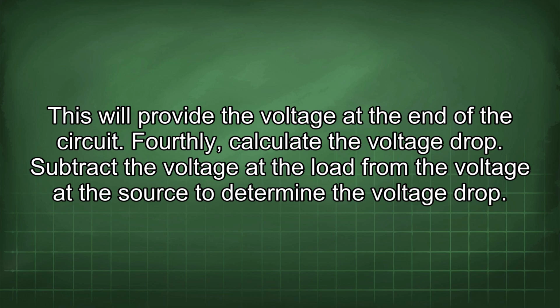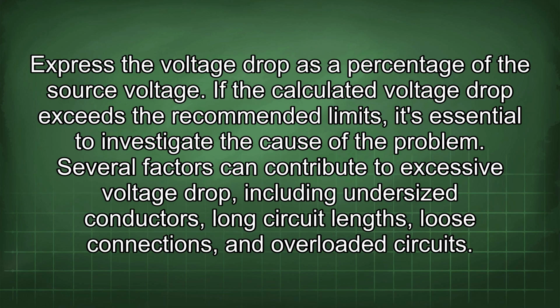Fourthly, calculate the voltage drop. Subtract the voltage at the load from the voltage at the source to determine the voltage drop. Express the voltage drop as a percentage of the source voltage. If the calculated voltage drop exceeds the recommended limits, it's essential to investigate the cause of the problem. Several factors can contribute to excessive voltage drop, including undersized conductors, long circuit lengths, loose connections, and overloaded circuits.